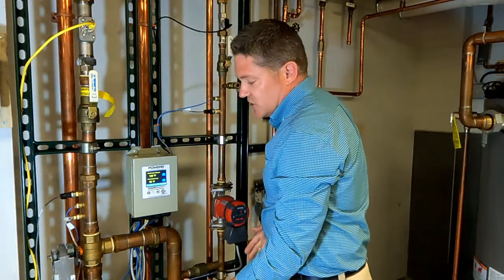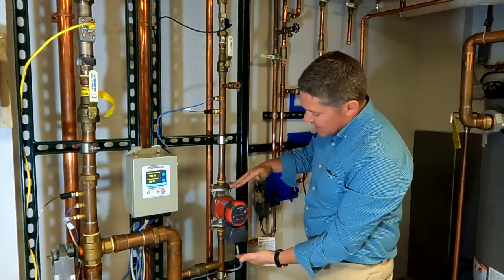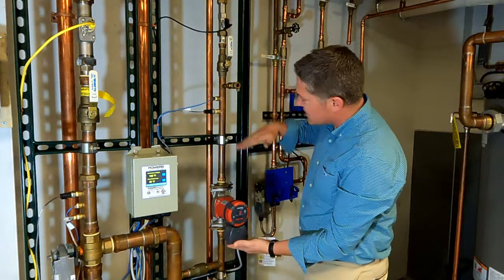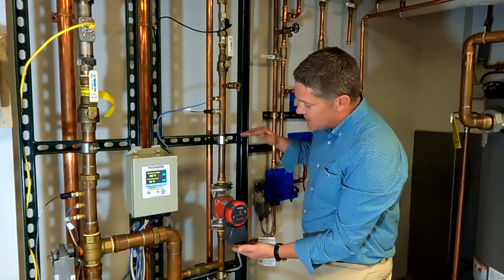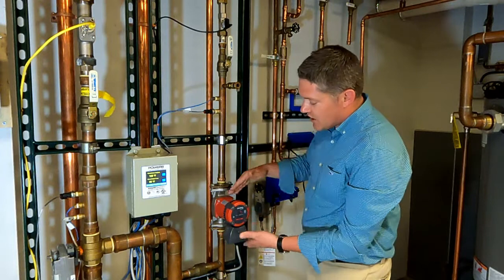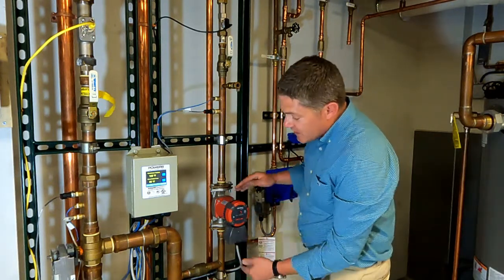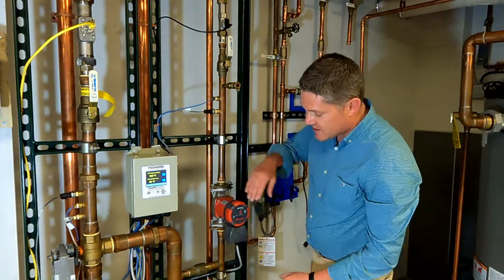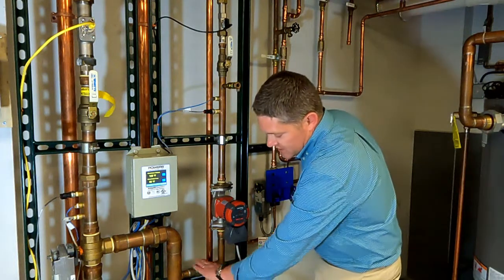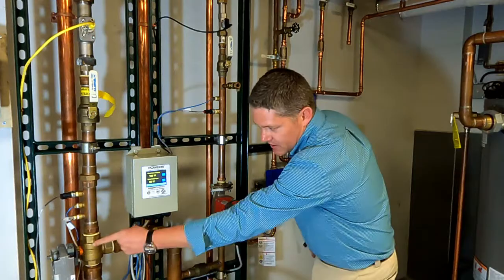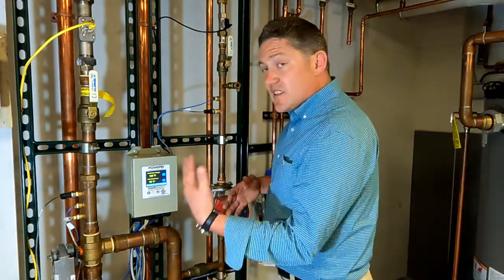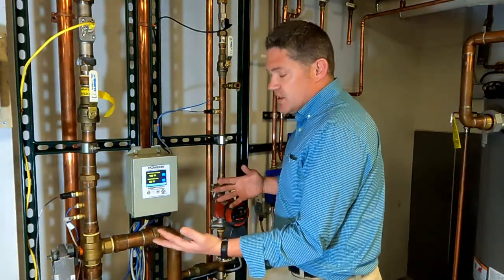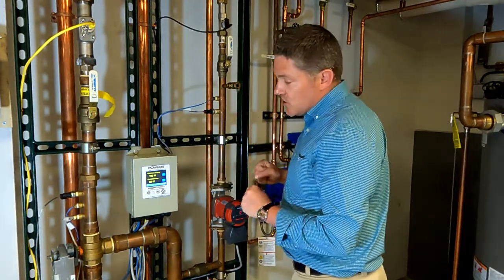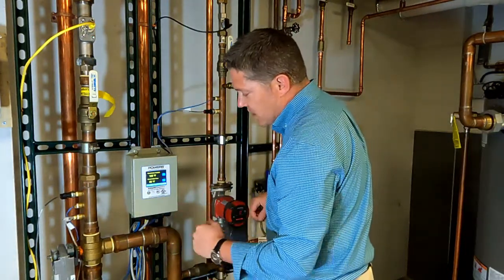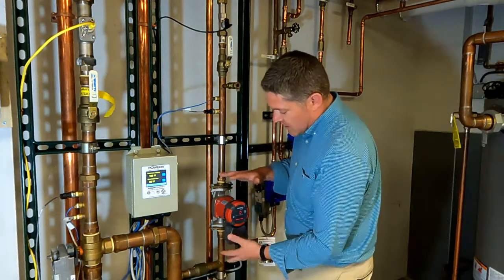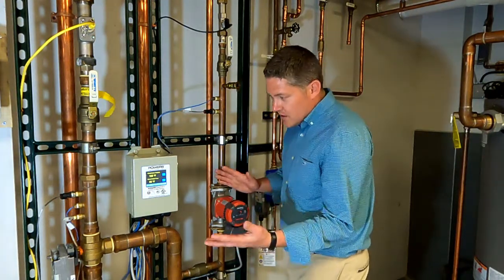So just 4 connections that you need to make. This is already all pre-piped. If you've ordered it without the pump, then this section of the skid right here, this piping, will just be a solid piece of pipe. You'll cut in and put in the recirc pump as needed. But that recirc pump needs to be placed just like it is here, on the return line before it hits this bridge. It goes back to the cold inlet of the mixing valve. So the self-balance part of it makes it a much easier setup and much easier install. Easy to keep balanced because it's a self-balanced valve. As long as it's piped correctly and the recirc pump is in the right spot, then you should be good to go.